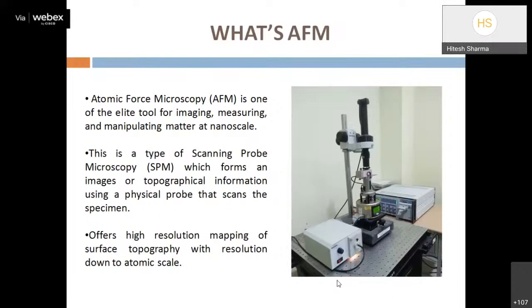One major advantage of AFM's probe technique over SEM and TEM is that there is no need for focusing. We can directly align the cantilever probe or cantilever tip to the laser and do mapping and topographic scanning. There is no need for electron beam focusing or magnetic lenses. AFM is also capable of providing height information of the sample, which is not possible with SEM or TEM, as we can directly measure the height and width of sample features.